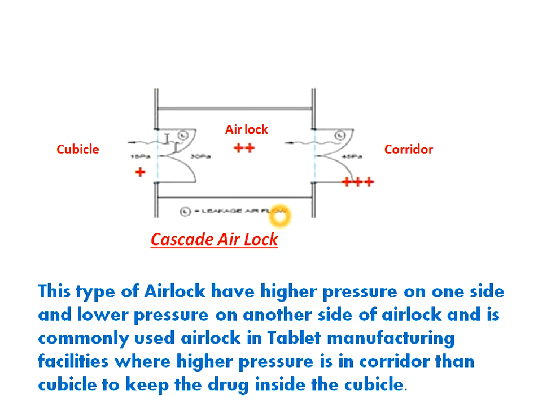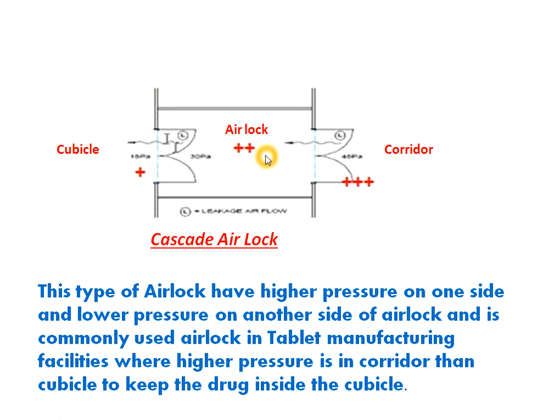First we will see cascade airlock. As shown in the cascade airlock diagram here, the cascade airlock has less pressure compared to the corridor pressure and more pressure compared to the cubicle. The cubicle is the manufacturing area where drugs or medicines are manufactured. Three-plus indicates higher pressure in the corridor, two-plus indicates the airlock, and one-plus indicates minimum pressure in the cubicle.